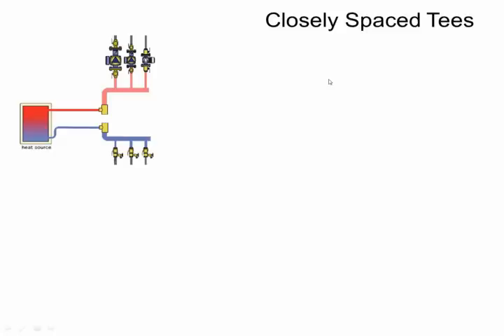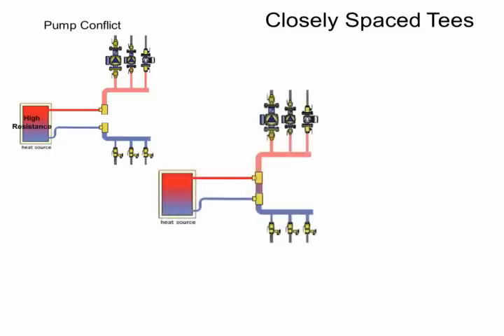So one way of preventing that is simply to create a path of flow for these pumps to go without having to go into the boiler. And we can do that such as this. But by doing so, now we've created a shortcut for the pumps. Now we don't have any way of getting heat from the boiler to our system. So we have to make sure we put a primary pump in. So now we have closely spaced tees. But they're not really closely spaced because we still have a gap here.